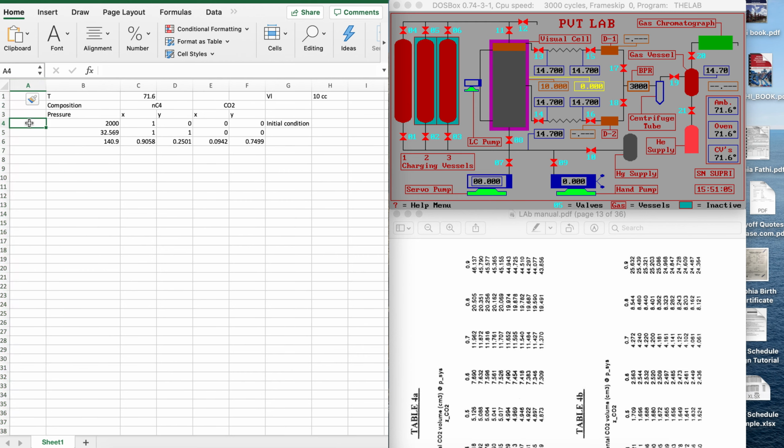So this was the initial condition, and then step 1, mixture 2, and let's say I have done all these, and now I'm in step 9. Okay. So in step 9, it says what I need to do is to add 46.137 cc's of mercury.